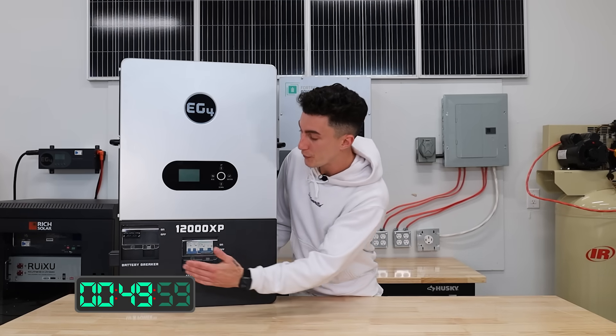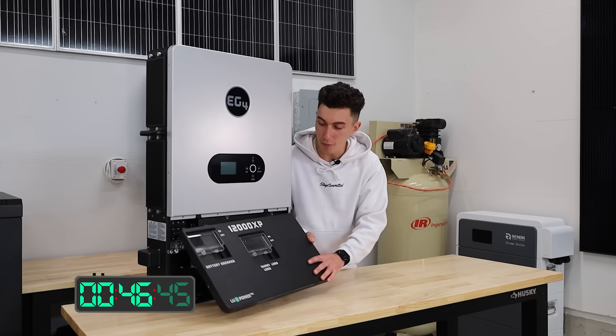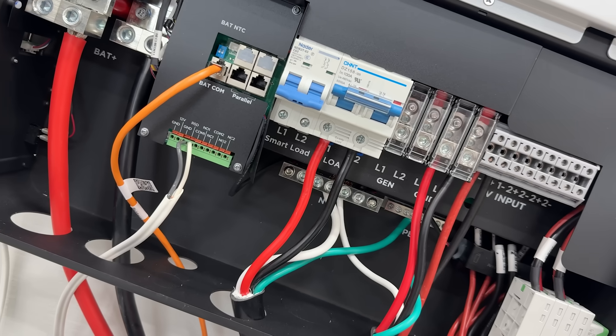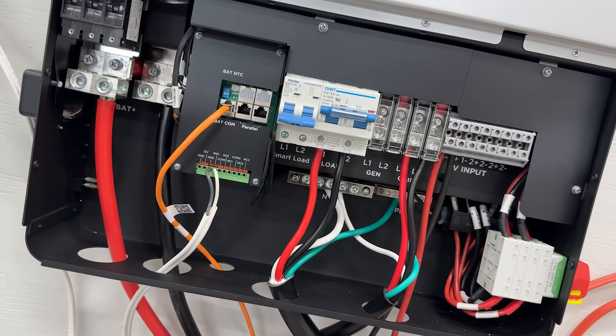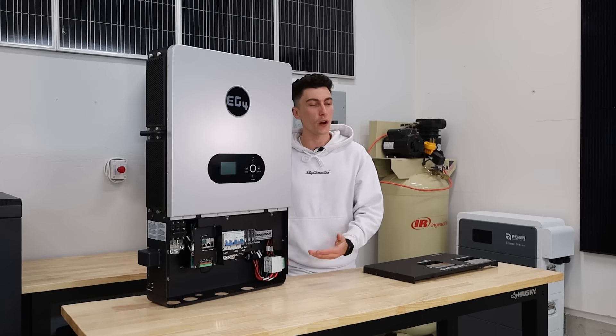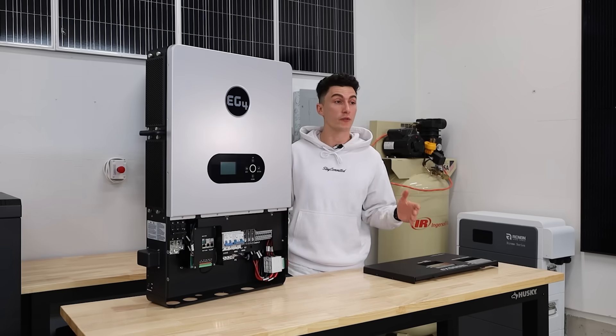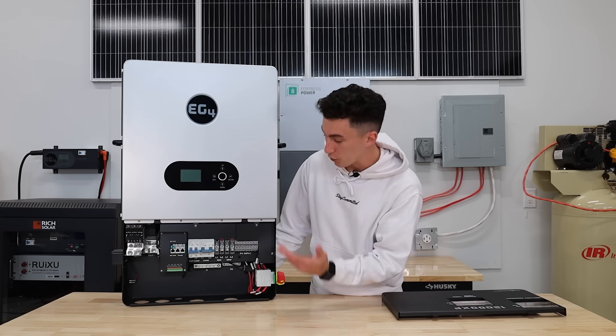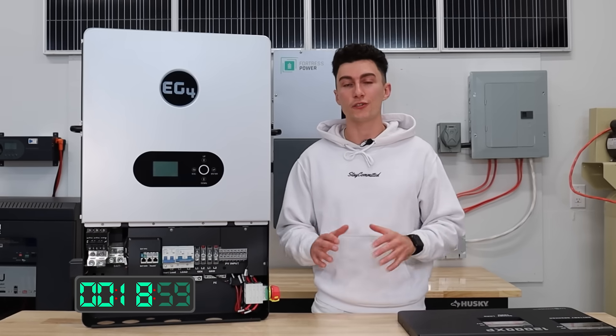On the right side you have your air intakes and Wi-Fi dongle connection. On the front, super simple: you have your load breaker, your smart load breaker — which is pretty cool — and your battery disconnects. Behind the panel, in true EG4 fashion, everything is logically laid out. You have your battery breaker, battery positive and negative connections, dry contacts, communications, and a generator connection. All terminals for your connections — smart load, regular load, grid input — are nice solid Allen key fasteners, easy to use.